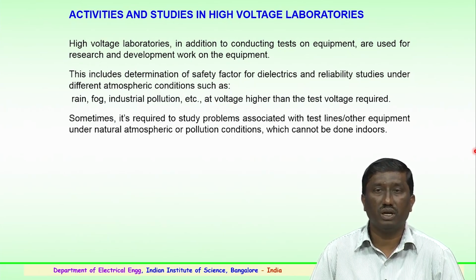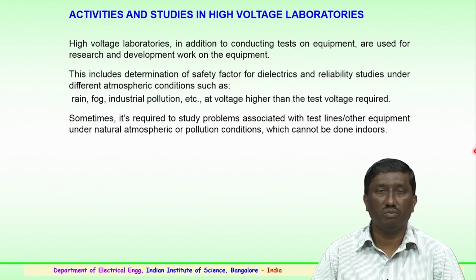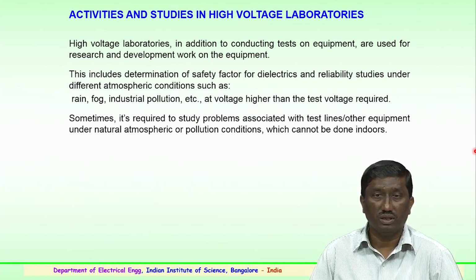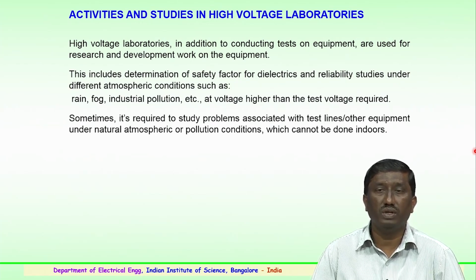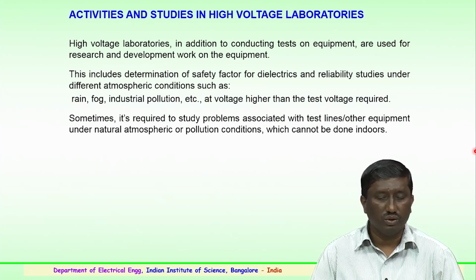in addition to the tests mentioned earlier on various equipments, the lab should cater for the research and developmental work which could be carried out on various equipments. This is very important. This could include determination of the safety factor, particularly for dielectrics, and reliability studies under different atmospheric conditions. This could be due to the effect of rain, fog, mist or the industrial pollution or contamination etc., at very high voltages than the test voltage required. So, sometimes the laboratory should be able to provide and is required to study the problems which could be associated with the test lines and other equipments under natural atmospheric or pollution conditions, which normally cannot be done indoors. So, very important. So, the laboratory should be able to cater to these requirements.